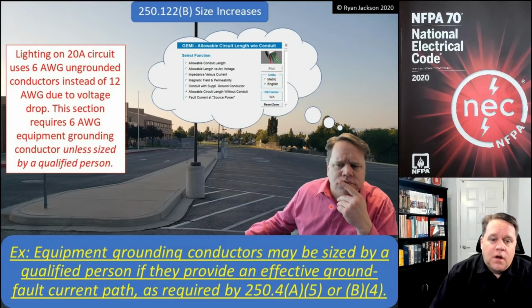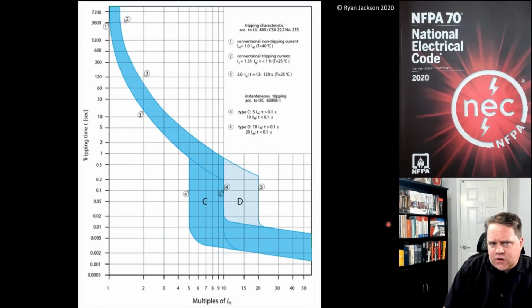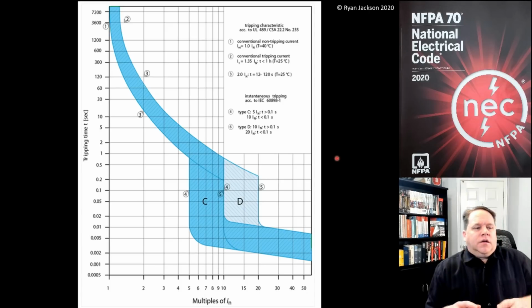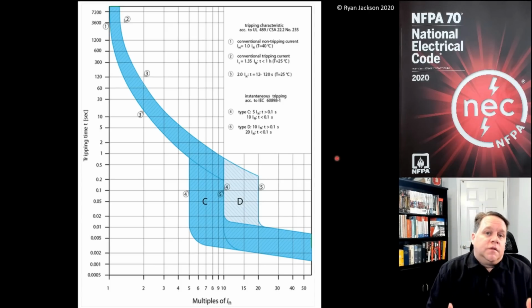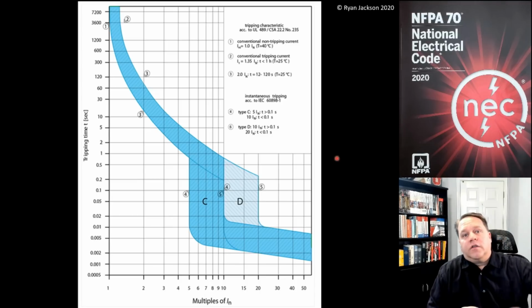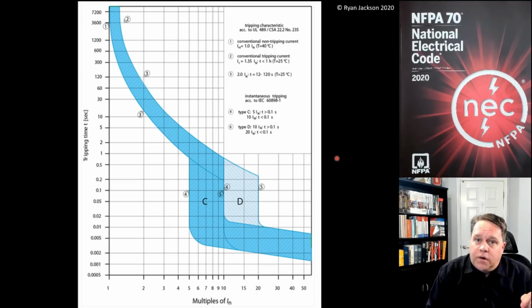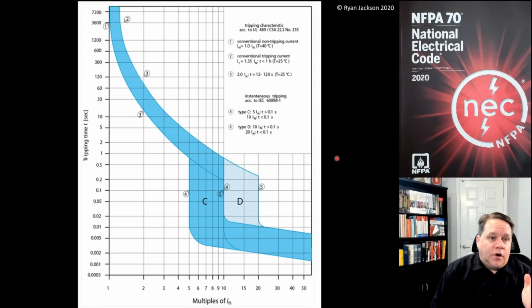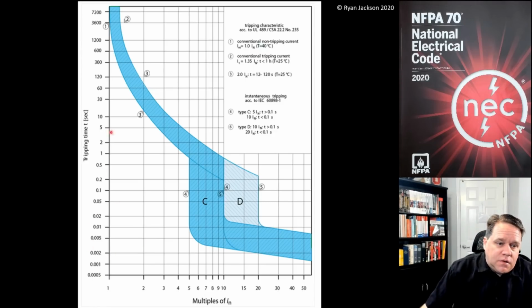So using this software, I should be able to ensure that the breaker or fuse will open and result in a safe installation. So before we get to the software, we need to figure out, how does a breaker or fuse work? Well, generally speaking, they work on the concept of inverse time and current, which means the higher the current it's exposed to, the faster it's going to open, right? If I have a 20 amp breaker and I put 20 amps on it, it will never open. And that's by design. So looking at our graph here, time is vertical and current goes left to right. And I want to point out really quick, this is not per scale.